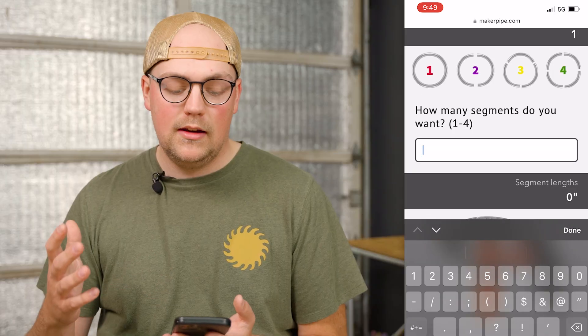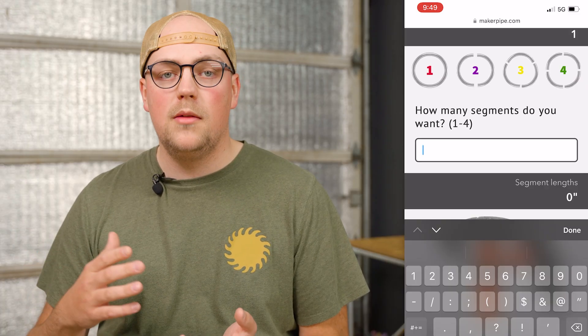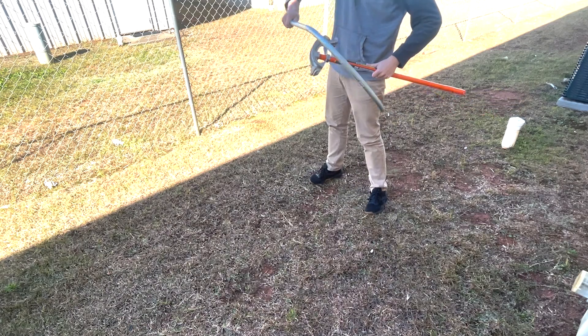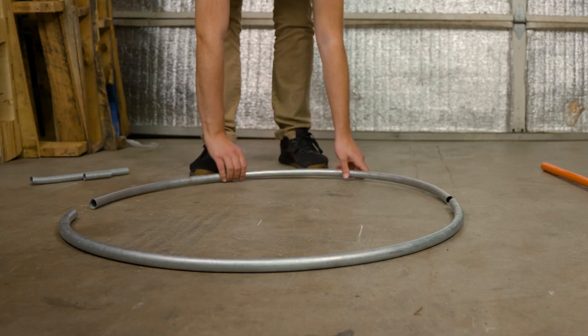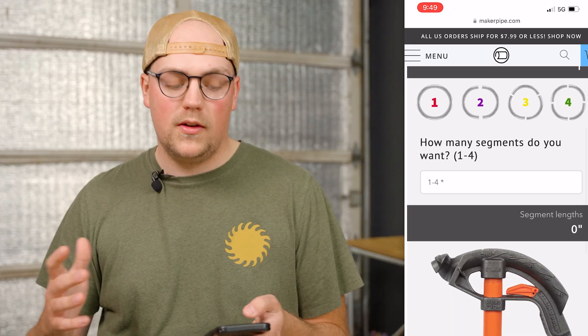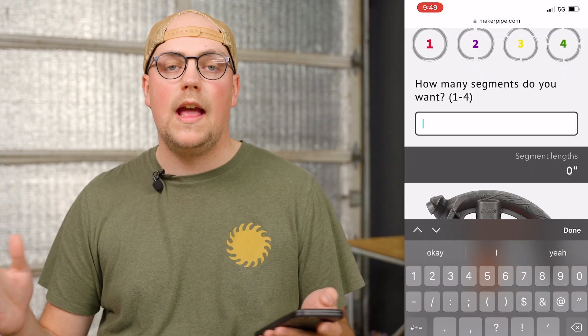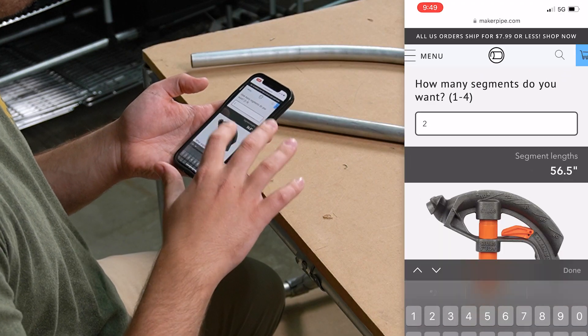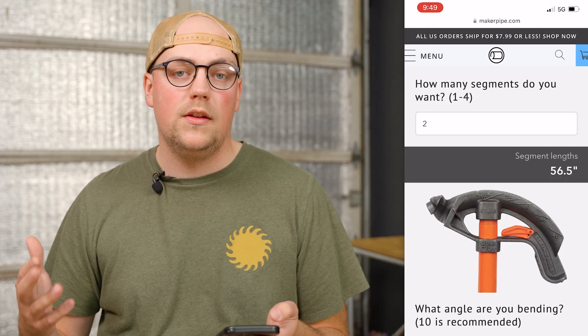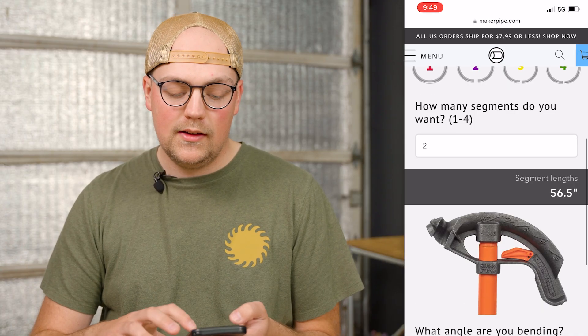You just want to choose how many segments you're going to break this up into. I don't recommend trying to bend a complete circle — it is possible but really challenging, especially towards the end. It's a lot easier to split it into halves, thirds, or fourths and then combine them together with couplings. I'm going to choose two segments, because two 180-degree halves makes a nice easy circle. That gives us an important measurement: the segment length, which is going to be 56.5 inches for each half.